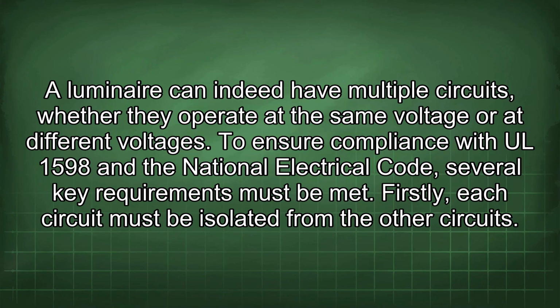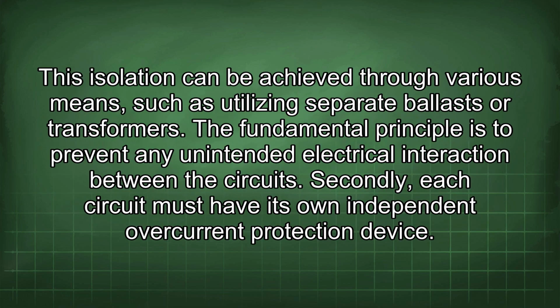A luminaire can indeed have multiple circuits, whether they operate at the same voltage or at different voltages. To ensure compliance with UL 1598 and the National Electrical Code, several key requirements must be met. Firstly, each circuit must be isolated from the other circuits. This isolation can be achieved through various means, such as utilizing separate ballasts or transformers. The fundamental principle is to prevent any unintended electrical interaction between the circuits.